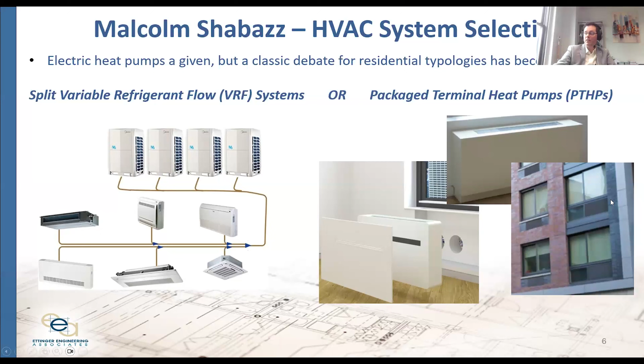for larger scale buildings like we do, the only cost-effective way to deploy VRF is with common condensing units. These condensing units on the roof are shared, and we typically vertically stack 5-10 apartments in a vertical apartment line on one condensing unit. There's a lot less refrigerant in the system, a lot less piping in the system, many fewer condensing units, and it's really the only practical way to do VRF in a large scale multifamily project like this.